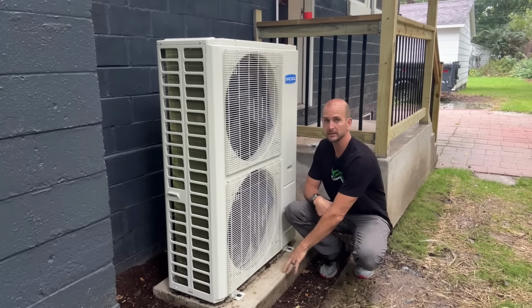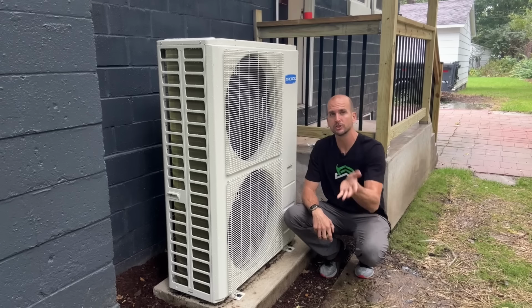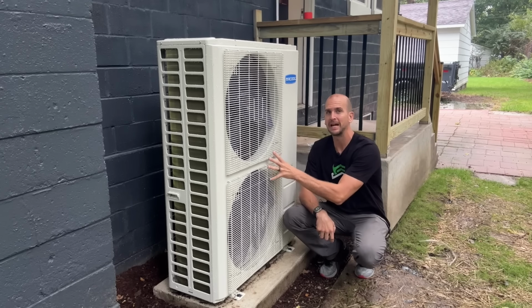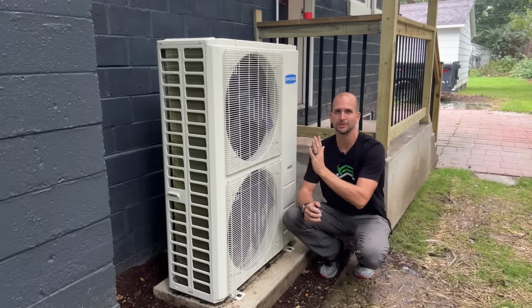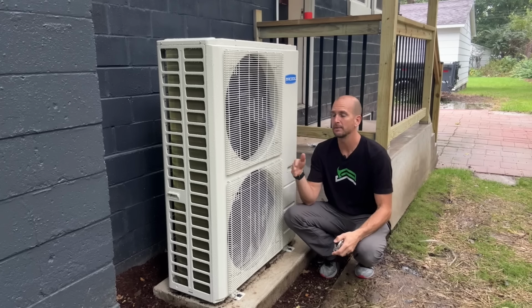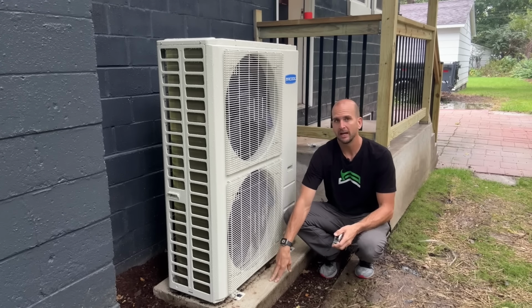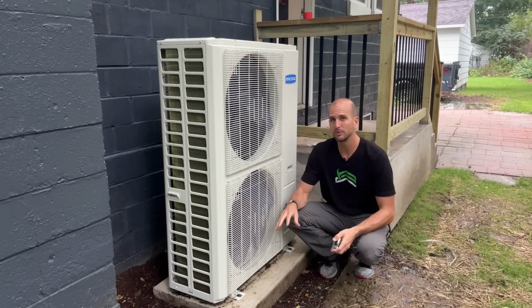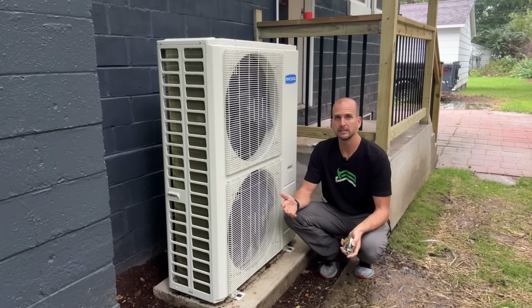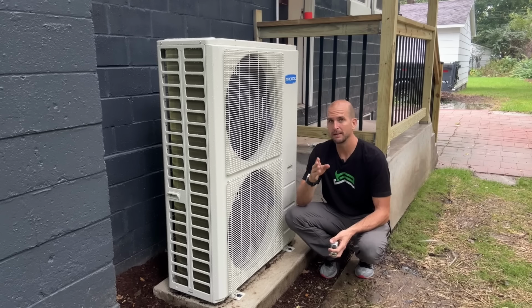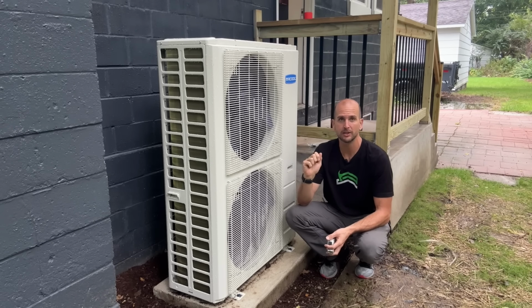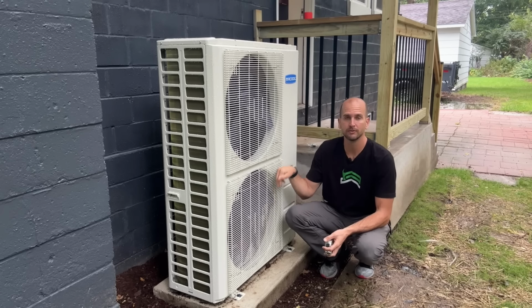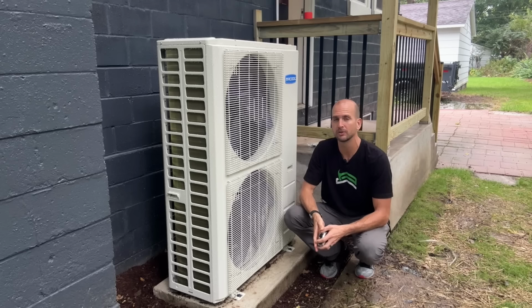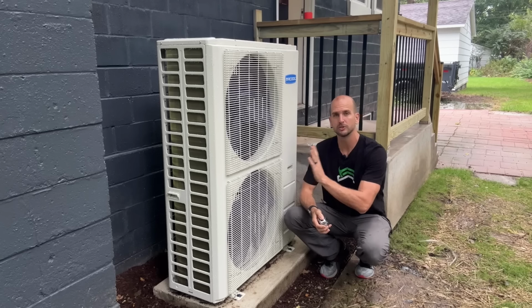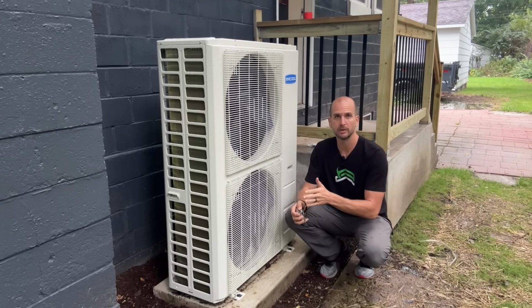Now, I didn't really document this concrete pad, but I want to give you a little bit of information just for your reference. It's great to put a concrete pad so this outdoor condenser actually has a secure foundation and it doesn't start leaning over time. There are some situations where you might be mounting it to brackets to your home, but if you have the ground mount like this, I do recommend a pad. This one is 24 inches by 48 inches long and 5 inches thick. 5 inches is a little aggressive, but I just wanted something secure. And then I use 4 Tapcon concrete anchors, 3/8 of an inch by 3 inches, to go ahead and secure each of the 4 mounting locations. And that gave me the secure mounting location spaced correctly from my wall. So do check the instructions just to make sure you have the clearance as recommended from Mr. Cool.